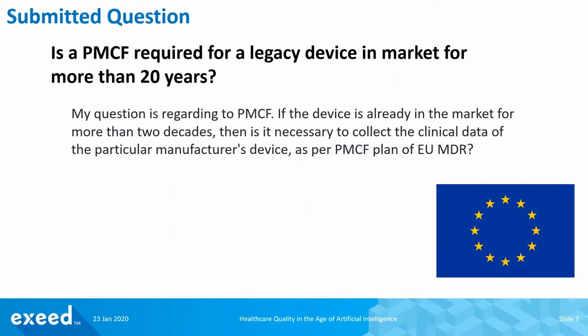They have given some information about how you are going to conduct your PMCF data. So whether we need to conduct any clinical study, particularly for any device which has been in the market for the last 20 years or more, or whether it is only sufficient to collect patient feedback, physician feedback, and literature from other, similar types of medical devices.